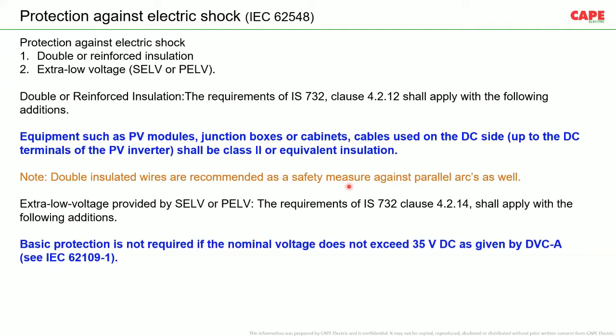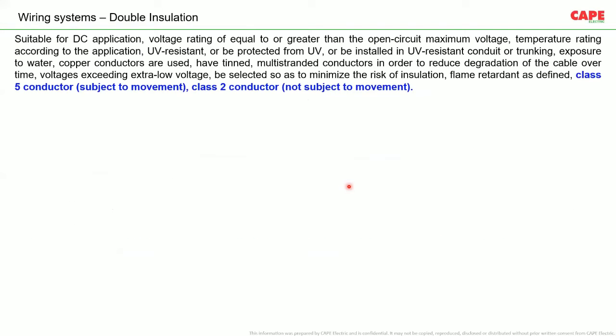I'm sure in a lot of places, especially in rooftop solar installation, due to cost pressure, the double insulated installations are not very much followed. So my recommendation is please note that this is the only shock protective measure available. So you must not violate the double insulation requirements on the DC side of the solar PV if the voltage is more than 120 volt DC. Example, how to make a double insulated wire, or if you use a normal wire, how can you achieve double insulation? These are also explained in the standard.